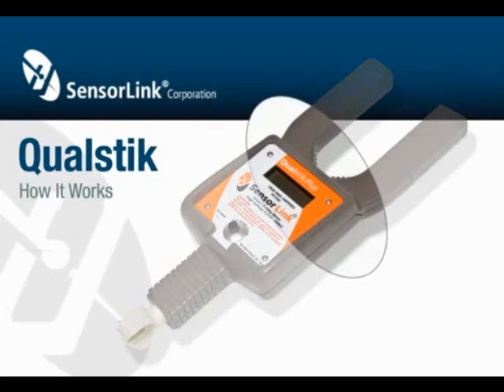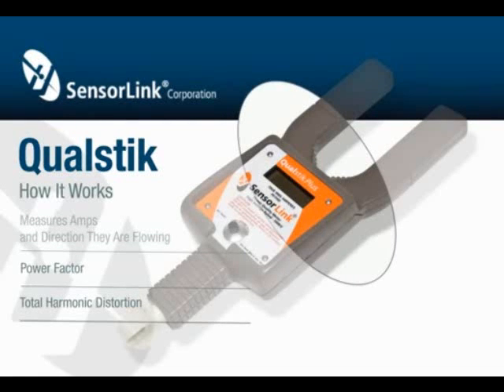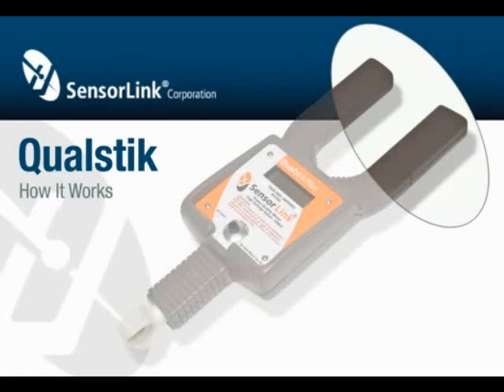The SensorLink Qualstik measures amps and the direction they're flowing, power factor, and total harmonic distortion. Current is measured using an inductive sensor that does not utilize magnetic materials and has no moving parts. The opening of the sensor is electronically closed, and external currents are also electronically rejected. This makes it easy to take current measurements.